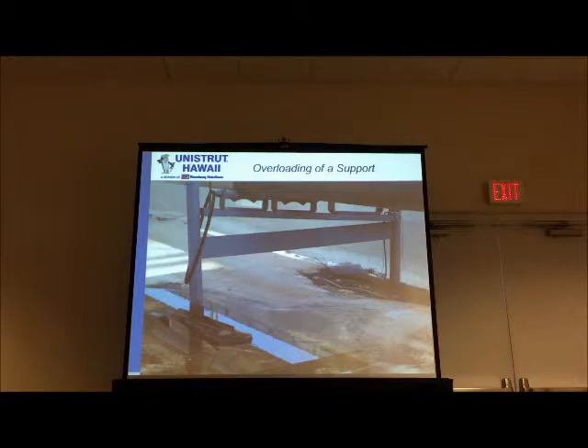Again, more examples of inadequate design supports. Now, this is a welded support. You can see we've also accounted here for movement of the pipe by having these rollers. Remember the first photo, we didn't have any rollers. In this photo we do, so someone went the extra step and said, this pipe is going to move, how are we going to accommodate for that? Well, they accommodated for it. We still have a problem.